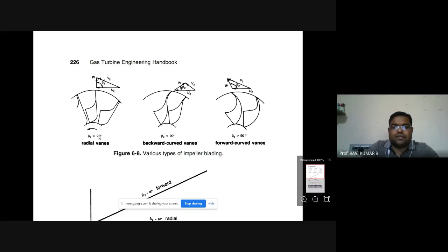So this is the comparative graph, which shows the pressure rise with respect to the mass flow rate for three different kinds of blades. Here is the forward curved blade, where a higher static pressure rise is taking place. This is the radial blade, where pressure rise is almost the same between the impeller and diffuser section. And this is the backward curved blade, where pressure rise is decreasing with the mass flow rate. So while pressure is increasing, mass flow rate is decreasing in the case of backward curved blades.